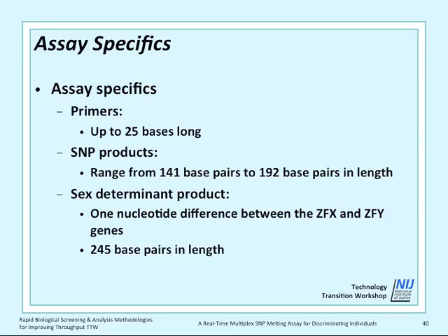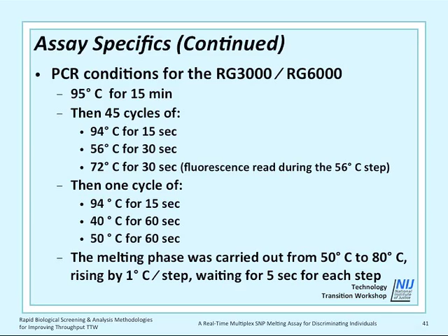The PCR specifications for this assay are shown on this slide. The PCR is 45 cycles using typical PCR parameters. The difference comes at the end. The last cycle melts the double-stranded DNA and reduces the temperature to allow the hybridization probes to reanneal. Afterwards, the melt phase is carried out from 50 degrees to 80 degrees C by increasing the temperature by 1 degree steps and waiting for 5 seconds at each step.